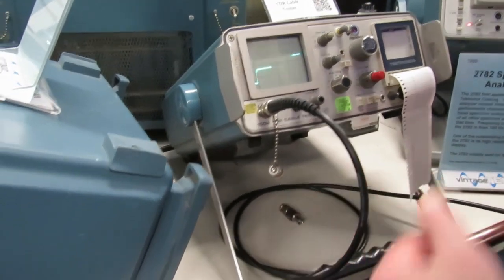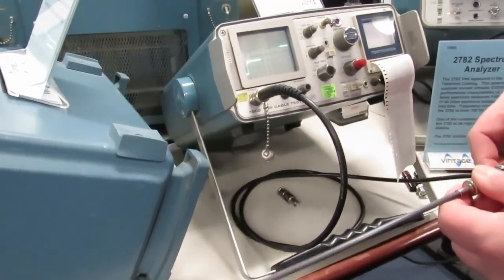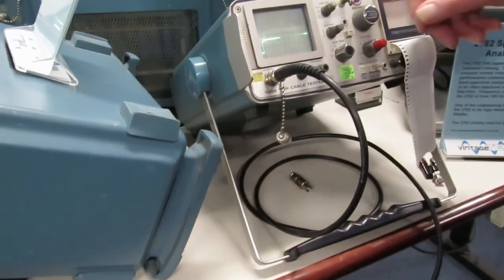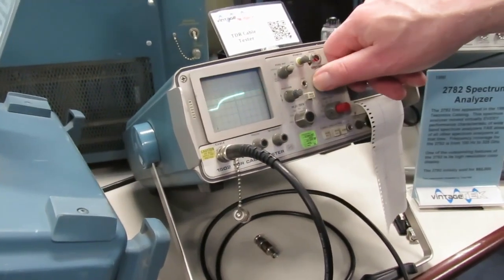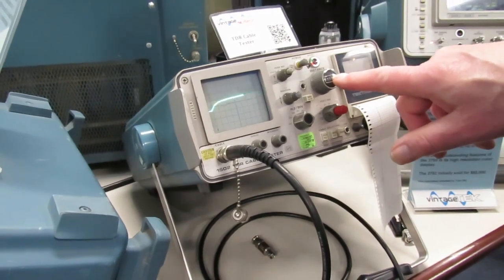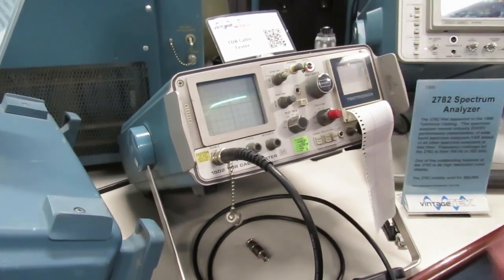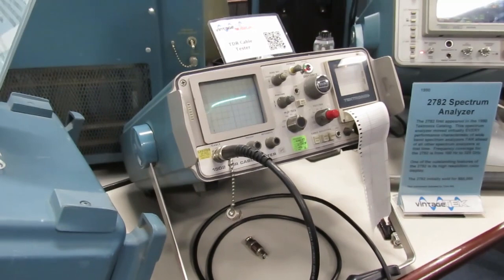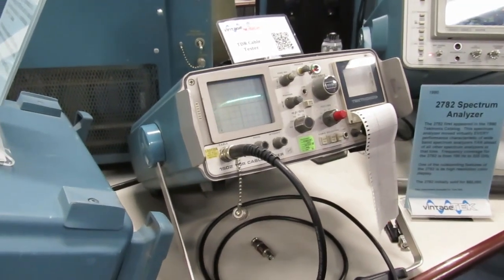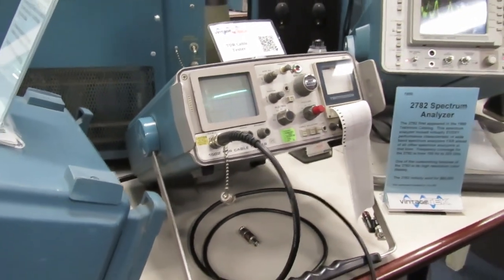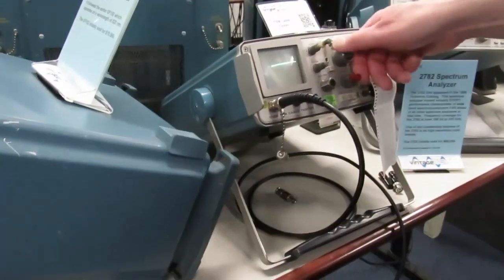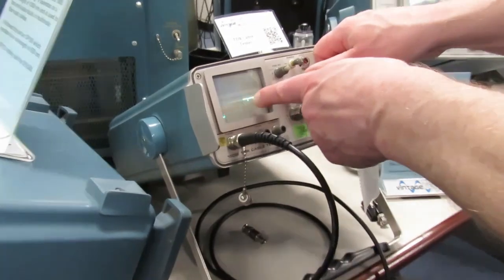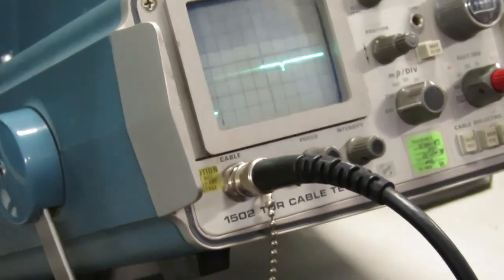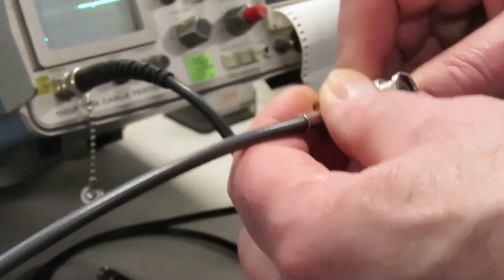and hook it up to the longer cable. Now we can dial out here, so that's 0 distance. Can dial out here, and I can read off 58 feet. And the fact that it's sloping up means it's a lossy cable. It would be sharper if it were a better cable. And so you can tell the length of the cable, but also you see some point along here about 5.5 feet. Well, this little connector is causing a glitch.